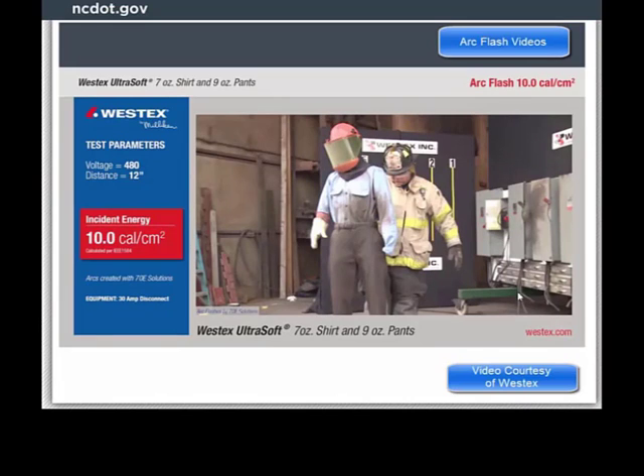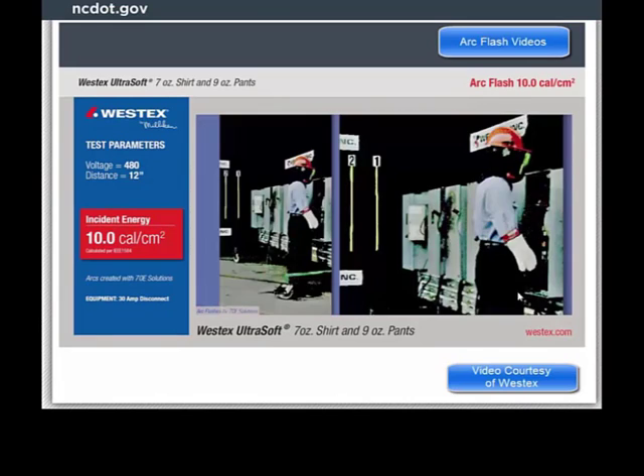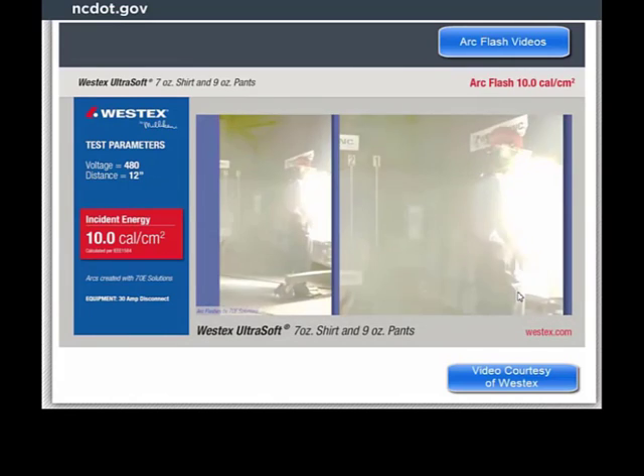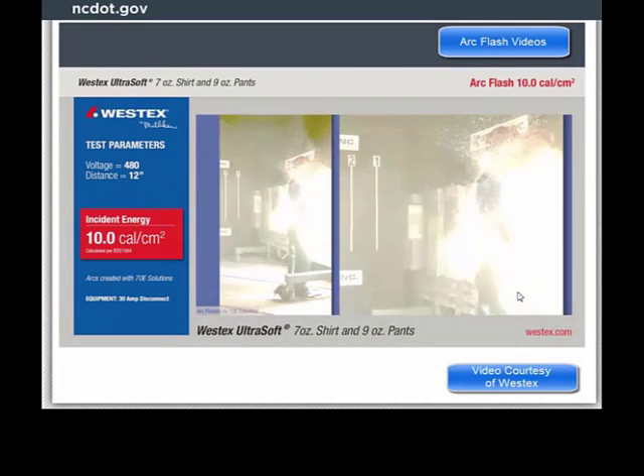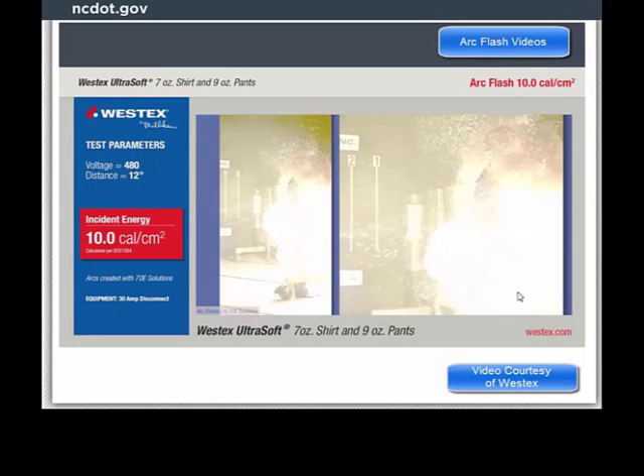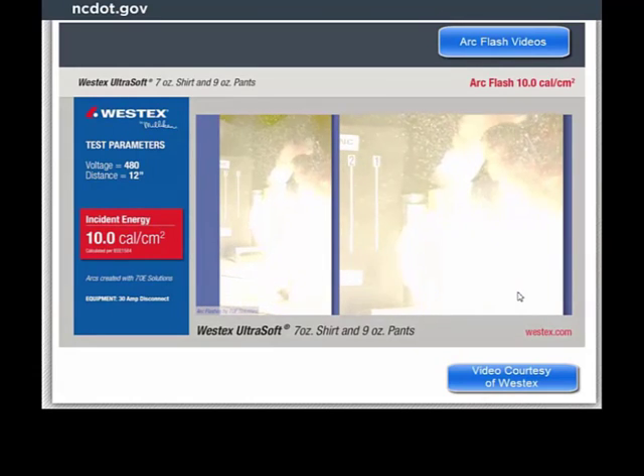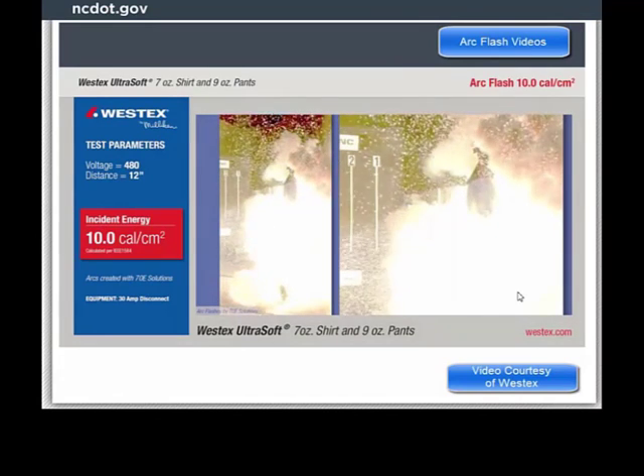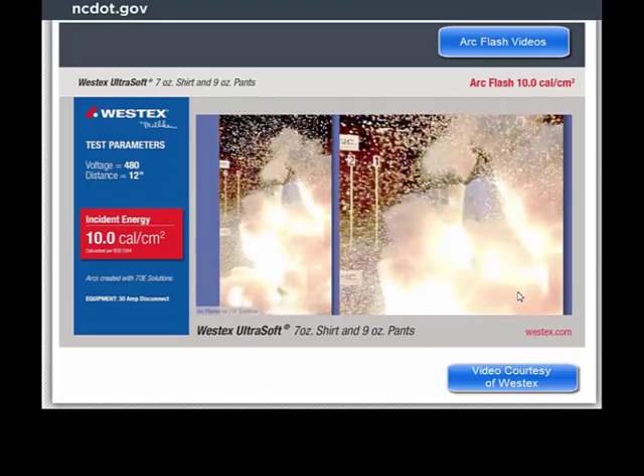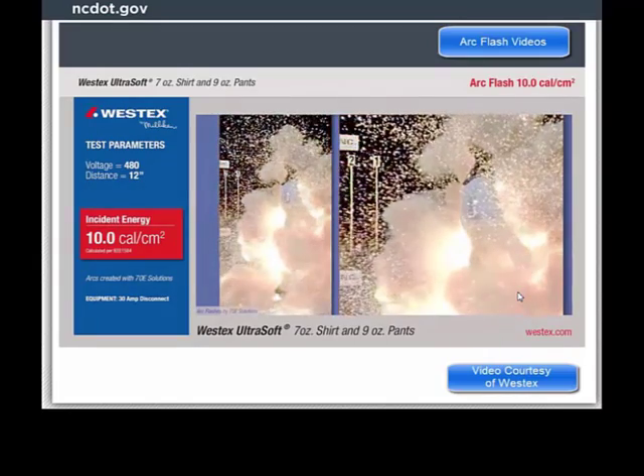Primarily an upper leg and lower torso event. And we'll get an even better look at that in our 3,000 frame per second split screen. There's a ton of molten metal coming out in this event at significant distances from the arc itself. If you look at the blue wall in the back with the stripes and the numbers, that's 15 feet from the mannequin, and you can clearly see chunks of molten copper hitting that wall through this entire event.